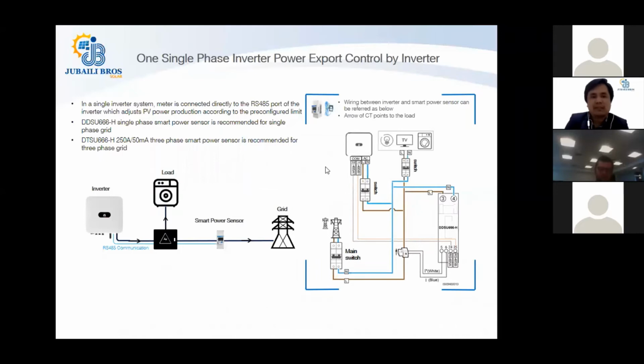So we go with the first case, the single phase inverter power export control. I would like to give you a quick brief of the slide. In the next slide, you will see similar configurations of the power meter connected in the system where there is the inverter and the grid. So what you will do is that you will have a current transformer which will be reading the current data on the grid side, and there will be voltage lines connected inside the AC combiner, which will also go to your power meter.